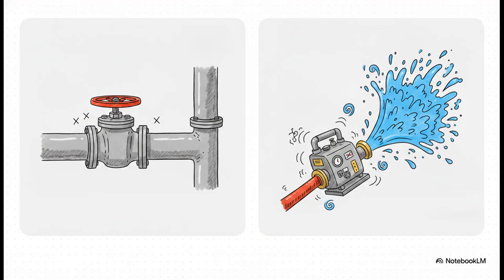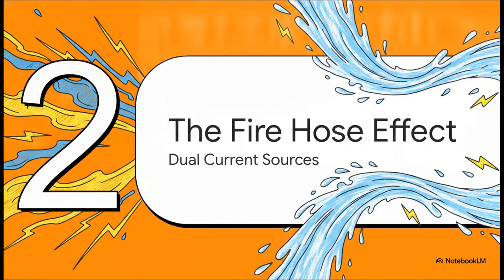Engineers who are new to generator protection sometimes make a really dangerous assumption. They try to apply a transformer-only protection philosophy to a generator-transformer block. Think of the grid as a water main, right? When a fault happens, opening that grid breaker is like instantly shutting off the main valve at the street. Boom, water stops. But the generator? The generator is a fire hose. Closing the street main doesn't stop the water that's already in the hose, and more importantly, it doesn't stop the pump behind it. The generator literally doesn't know the grid breaker opened. It will happily just keep feeding that fault until the machine itself physically winds down and is explicitly told to stop. Which brings us right to section 2, the fire hose effect.